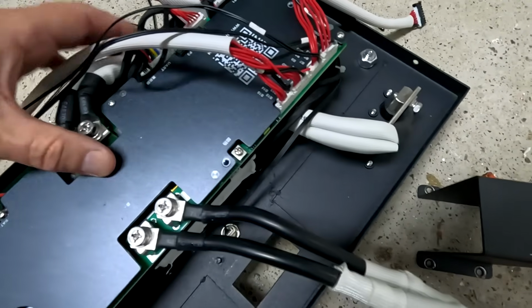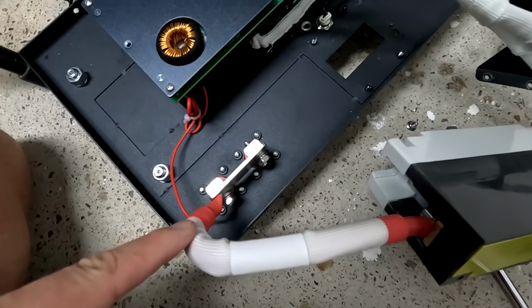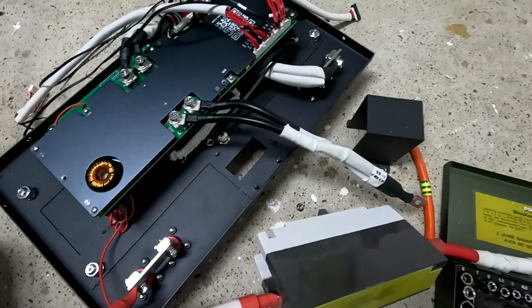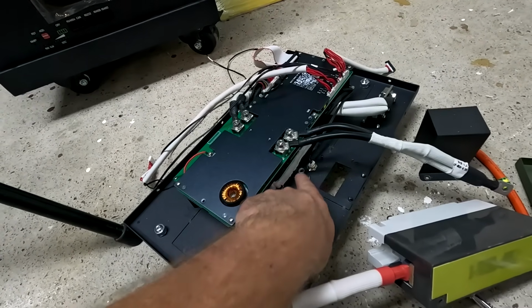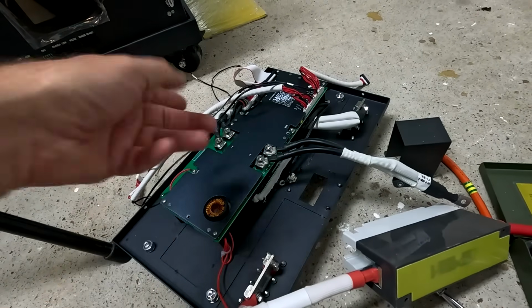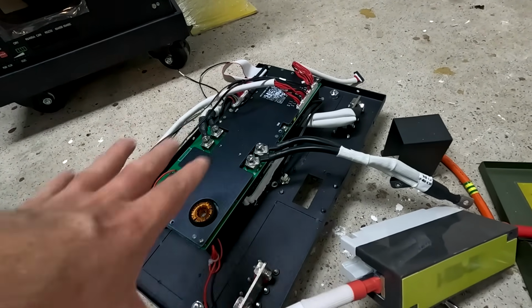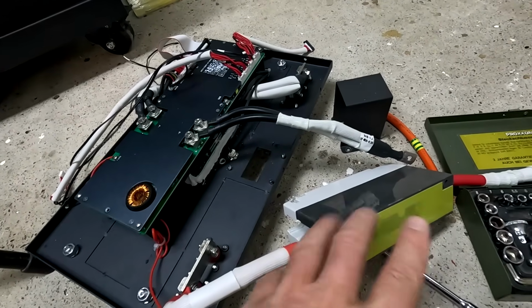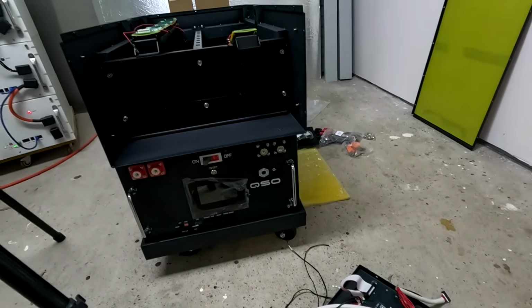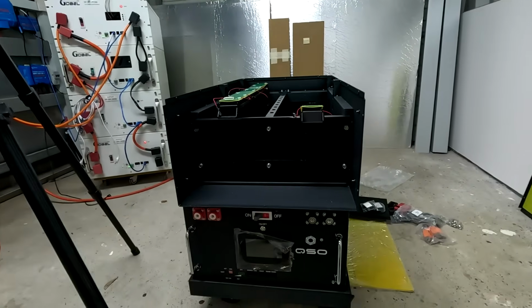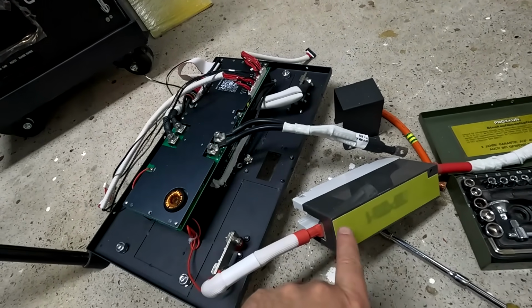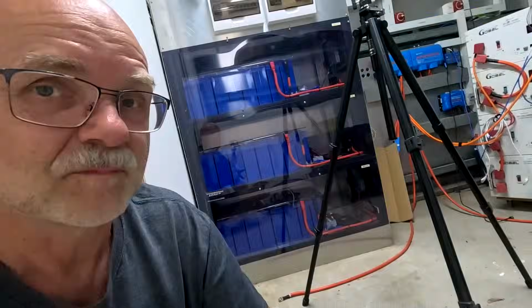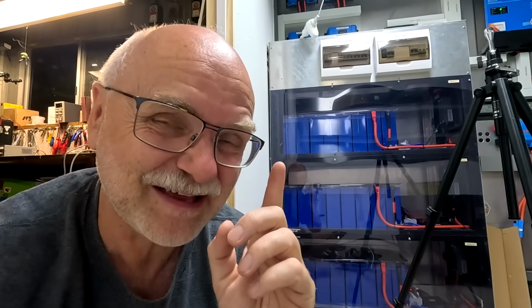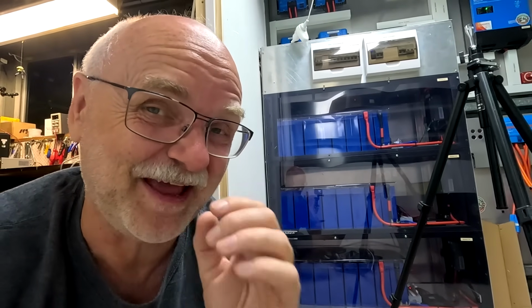So cable lengths are good in general, so they're not too tight. The bend is not too tight here. That all doesn't look too bad. But still, we've got some weird design choices here with the display, for example. Cables are a bit too thin for my taste. So I would definitely recommend to install another fuse in here, because this one may not be able to protect whatever battery you build. You have to probably factor in a 15 to 20 kiloamp short this battery can deliver. So the breaker should have at least 20 or 25 kiloamp breaking capacity. And so should your fuse. I'll make a separate video about selecting the right fuse for your batteries. It is very interesting what I actually found.